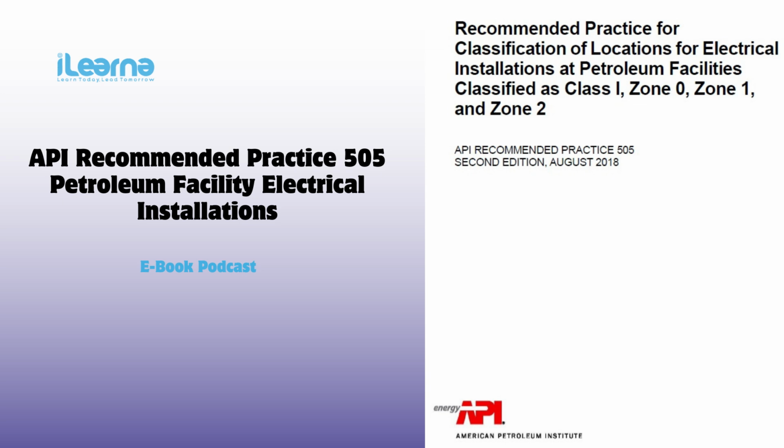So Zone 2 must be the least hazardous of the three. Exactly. Zone 2 is where a flammable atmosphere is only likely under abnormal conditions, like if there's a major equipment failure or a big spill. So it's still important to have safeguards, but the overall risk is much lower. So it all comes down to how likely it is for a flammable atmosphere to form and how long it might last. Exactly. The more likely and the longer it lasts, the higher the risk, and the more stringent the safety requirements. That makes sense.